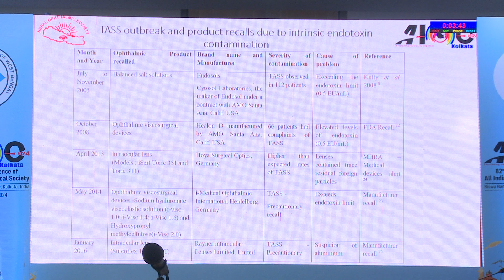So, take home messages: there should be a written SOP, a protocol for instrument cleaning and sterilization. We should not allow any cannulated devices to dry till the cleaning station. We should keep them moist. Rinse, flush, air flush, and completely dry before storing. I will wash before inserting into the eye. Follow the manufacturers' instructions. We should proactively ask the manufacturer for the endotoxin level of any substances entering the eye, from irrigating solution to OVDs to IOL, periodically. Judicious reuse of single-use devices.